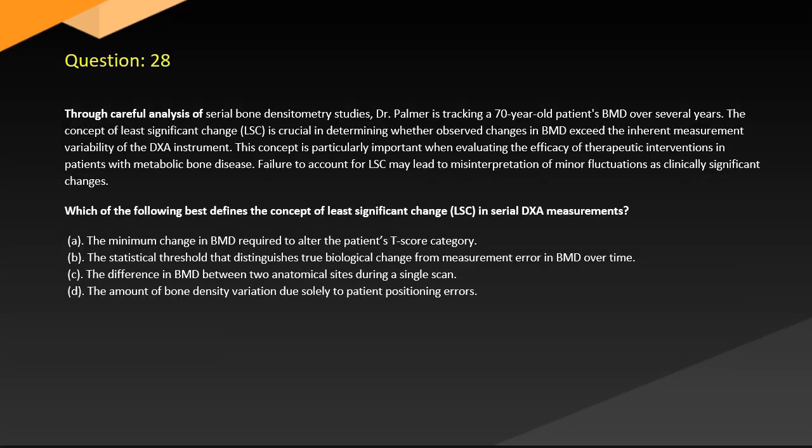Question 28. Through careful analysis of serial bone densitometry studies, Dr. Palmer is tracking a 70-year-old patient's BMD over several years. The concept of least significant change, LSC, is crucial in determining whether observed changes in BMD exceed the inherent measurement variability of the DXA instrument.